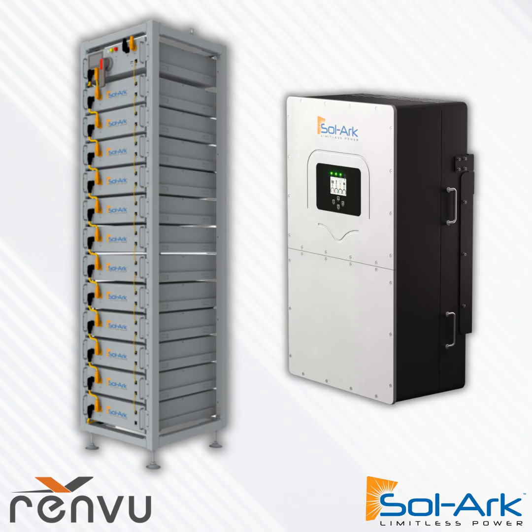Pros and cons of low voltage and high voltage: high voltage is necessary to deliver a commercial building's worth of power. 48 volt is sufficient to deliver a residential, even large residential, building's worth of power. The ampacity of large residential starts to get a little unwieldy, but that's really when you start getting to battery bank sizes well above 100 kilowatt hours.